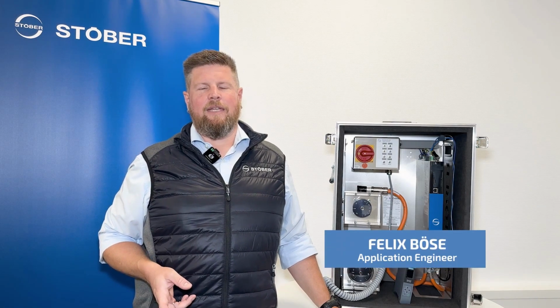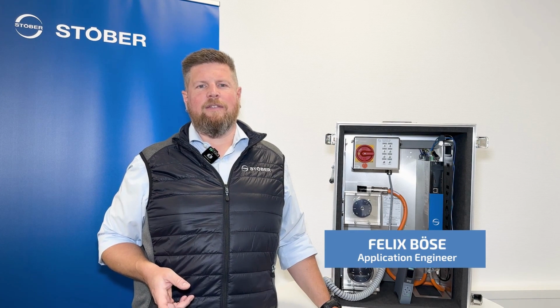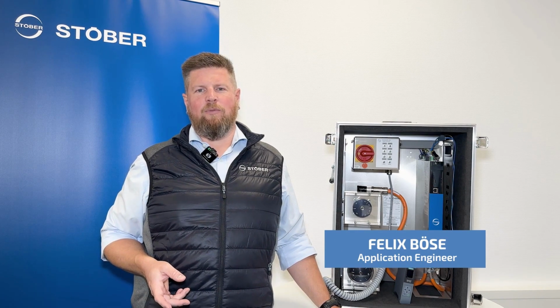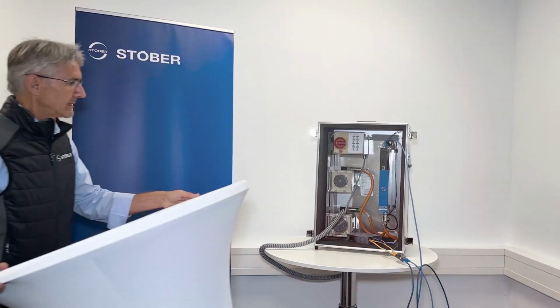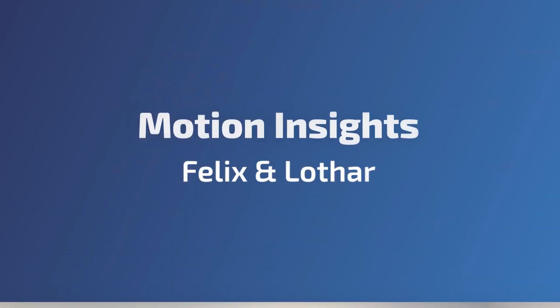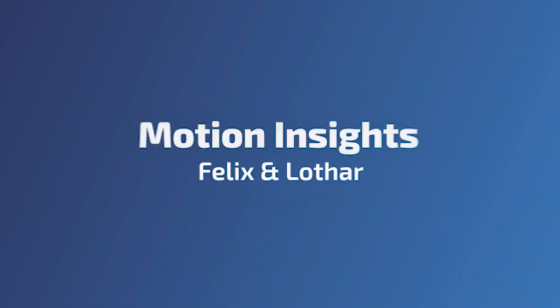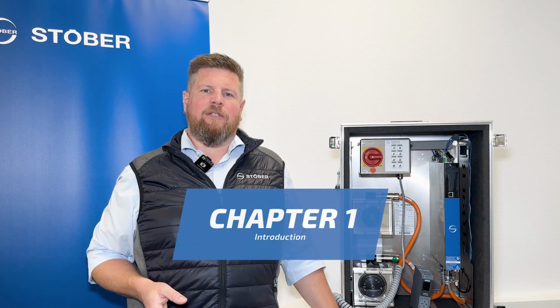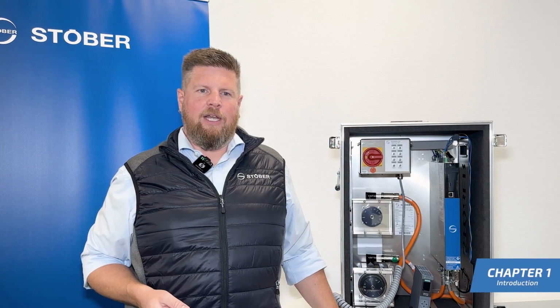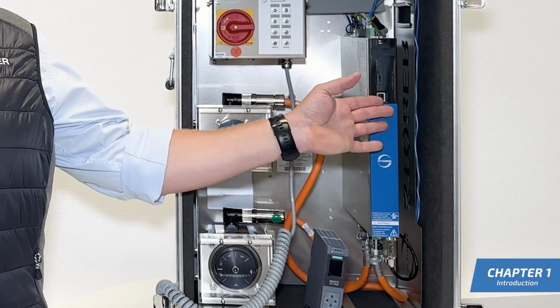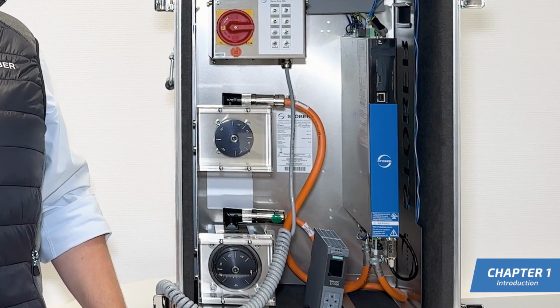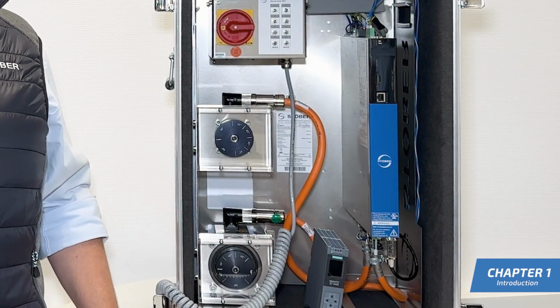I'll show you step by step how you commission a STOBER system via PROFInet using the PROFIdrive profile. To help you follow the individual steps easily, I'm working with an exemplary system environment. A STOBER drive controller from the SC6 series, a Siemens S7-1500 controller, and the corresponding commissioning software.